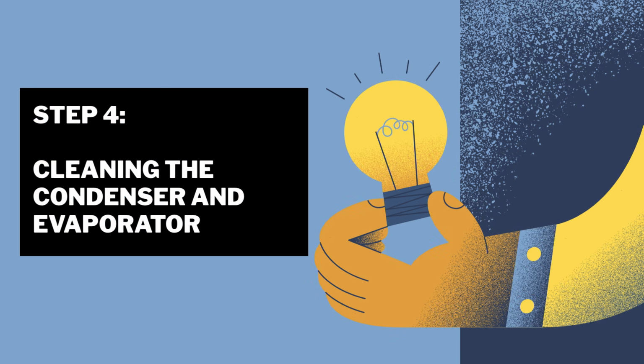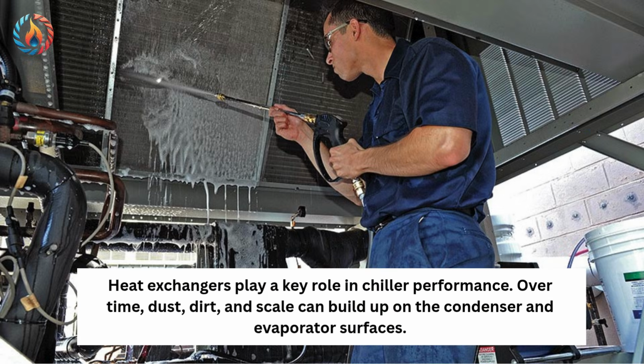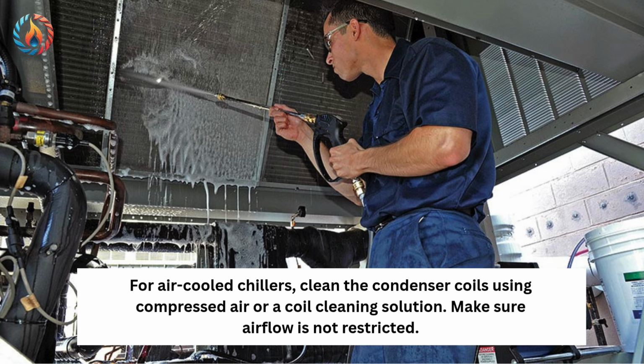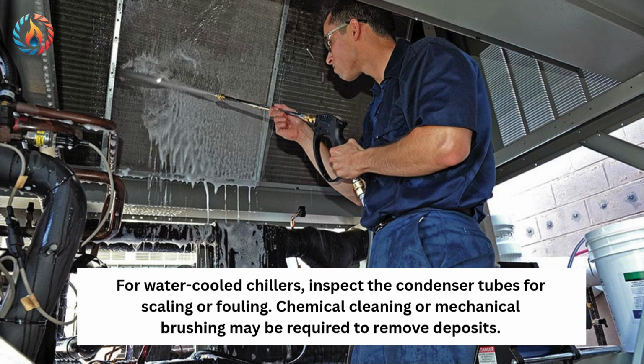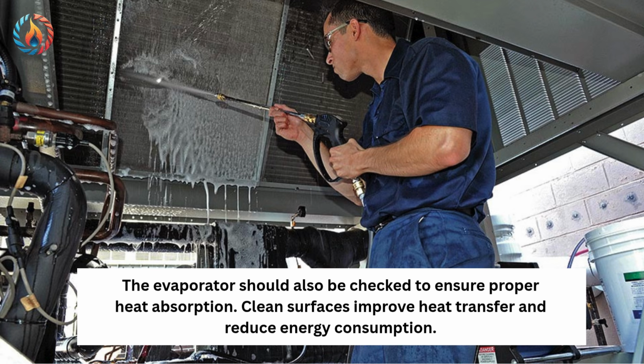Step 4. Cleaning the condenser and evaporator. Heat exchangers play a key role in chiller performance. Over time, dust, dirt, and scale can build up on the condenser and evaporator surfaces. For air-cooled chillers, clean the condenser coils using compressed air or a coil cleaning solution. Make sure airflow is not restricted. For water-cooled chillers, inspect the condenser tubes for scaling or fouling. Chemical cleaning or mechanical brushing may be required to remove deposits. The evaporator should also be checked to ensure proper heat absorption. Clean surfaces improve heat transfer and reduce energy consumption.